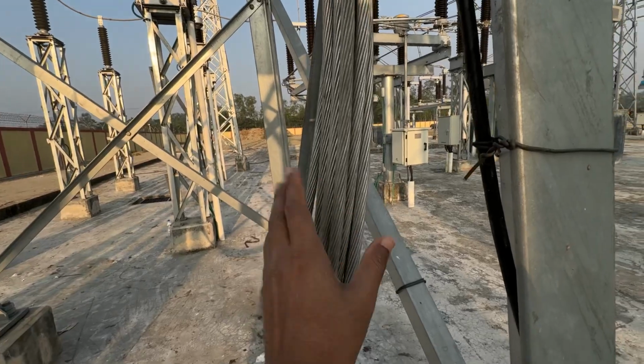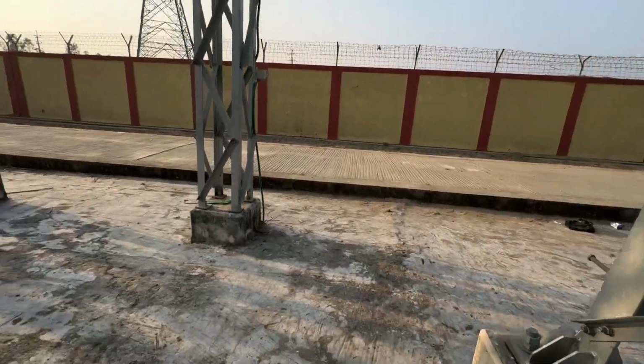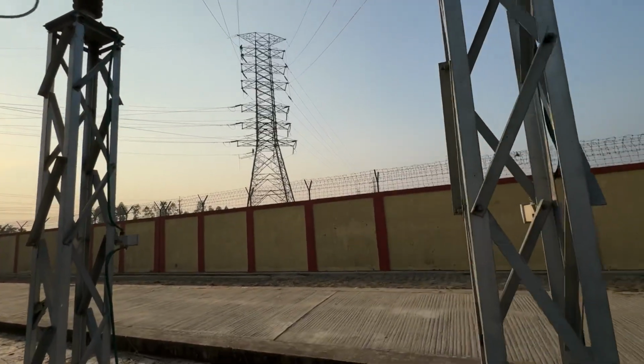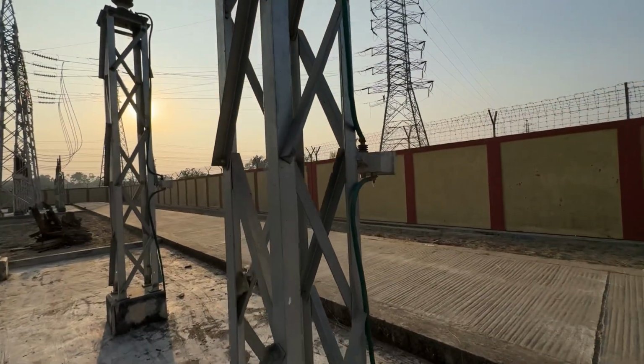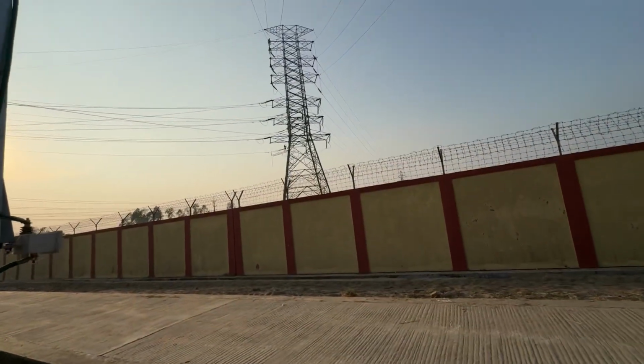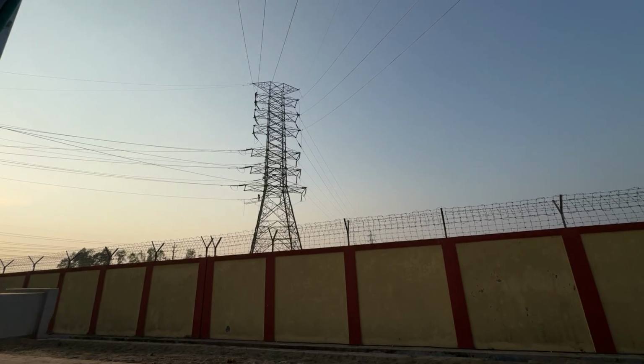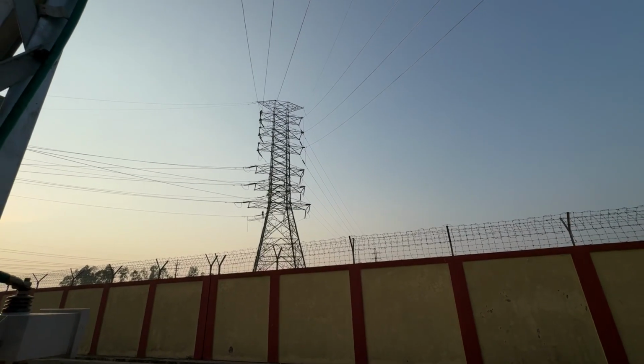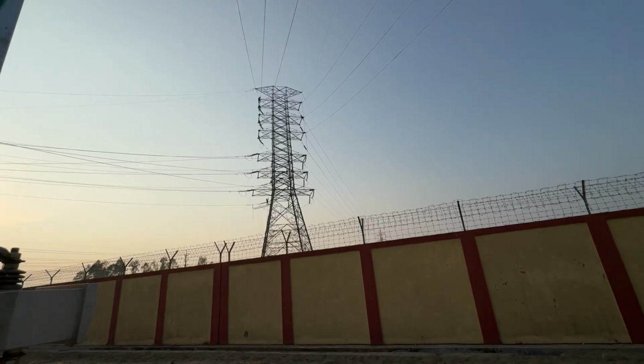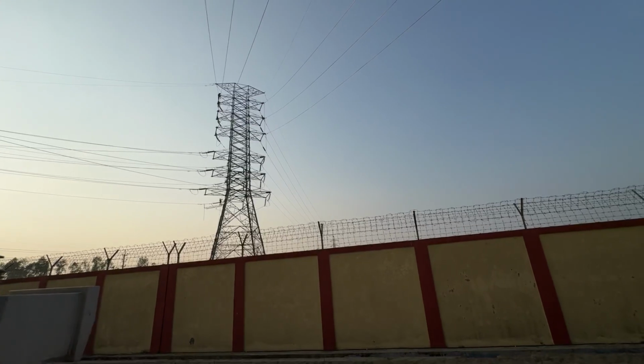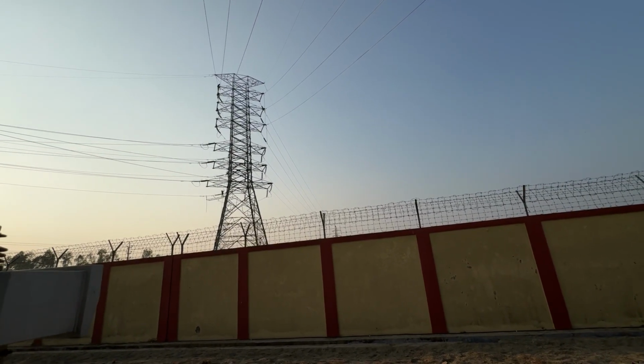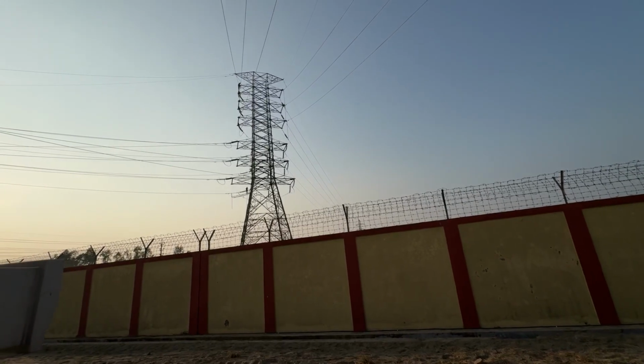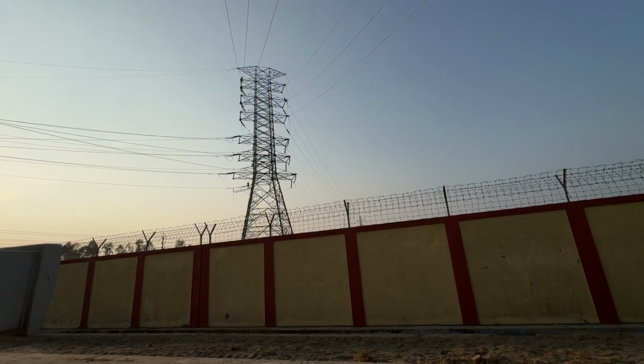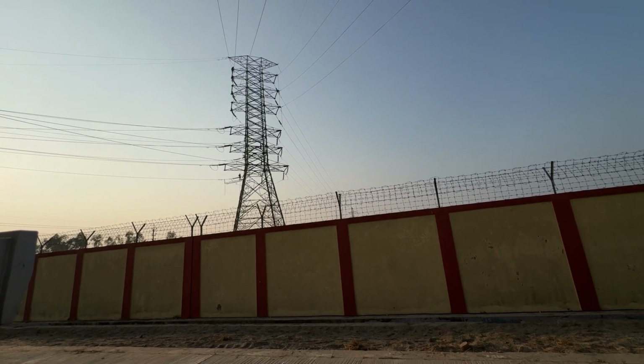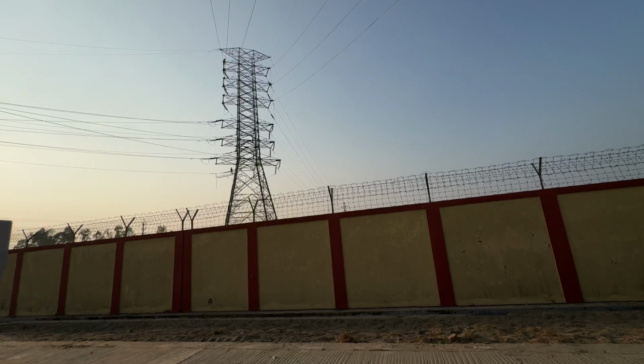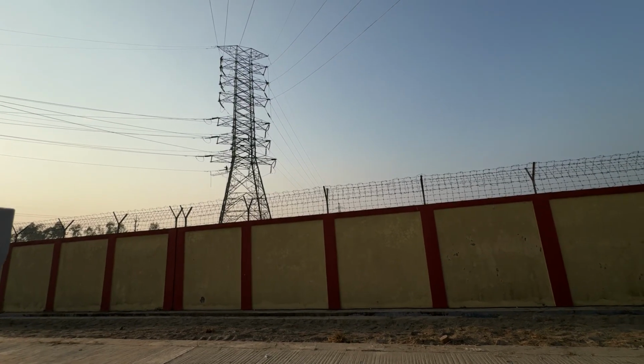This is the OPGW, optical fiber ground wire. Actually, in earlier days only earth wires were used above the conductor at towers, but nowadays one earth wire is a direct earth wire, and the second is not just an earth wire. Instead, OPGW, optical fiber ground wire, is used. Optical fiber is used for communication purposes, and the ground wire acts with the same function as the earth wire.